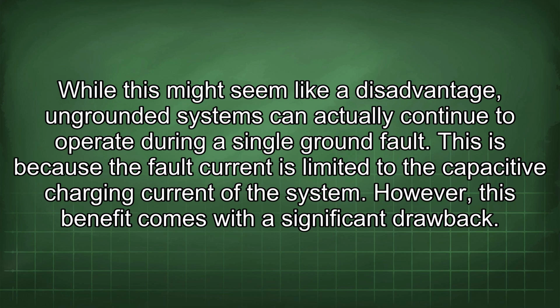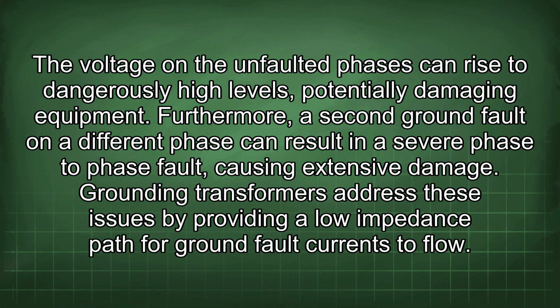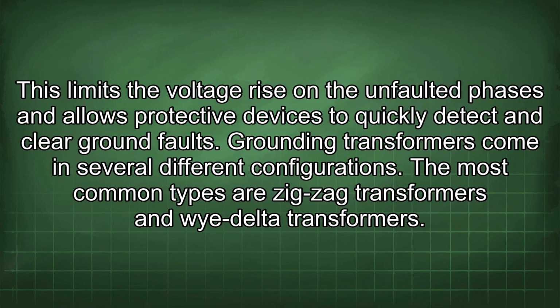However, this benefit comes with a significant drawback. The voltage on the unfaulted phases can rise to dangerously high levels, potentially damaging equipment. Furthermore, a second ground fault on a different phase can result in a severe phase-to-phase fault, causing extensive damage. Grounding transformers address these issues by providing a low impedance path for ground fault currents to flow. This limits the voltage rise on the unfaulted phases and allows protective devices to quickly detect and clear ground faults.